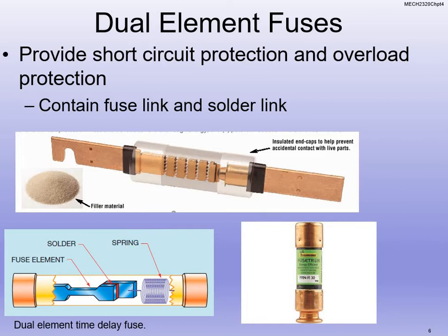So we have something called a dual element fuse. This is a little bit different than any of the fuses that we have in class. What happens here is it's kind of like solder, and it uses a type of solder essentially. When we were soldering circuits in class, you would put the solder on the iron, and solid solder is soft, it's flexible, but it still had to get to a certain temperature to melt and liquefy. That's kind of what happens with this. We send enough current through it, it will heat up, and once it gets to that specific temperature and the solder starts to liquefy, it'll slide apart. It allows it to slide. So it's a time delay fuse, because sometimes we have an inrush current and we don't want to trip the motor, but then the motor can get to speed and the inrush current drops back down to normal operating. So we don't want to constantly replace fuses. We have a time delay.